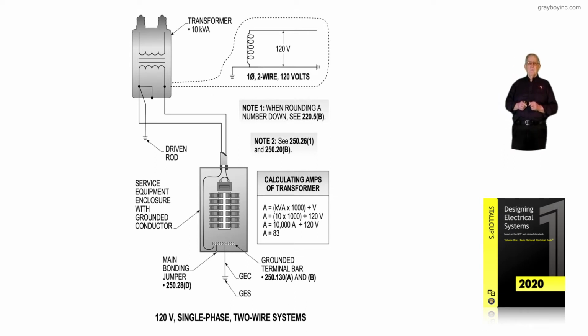So calculating the amps of the transformer is in the boxed in information right below note 1. Notice the amps can be found by taking the kVA times 1,000 and dividing it by the voltage. Amps is equal to 10 kVA times 1,000, and we use the 1,000 to get rid of the K and have in the formula just VA. So when we divide 10 times 1,000 by 120 volts, then the amps on the ungrounded conductor is 83 amps.